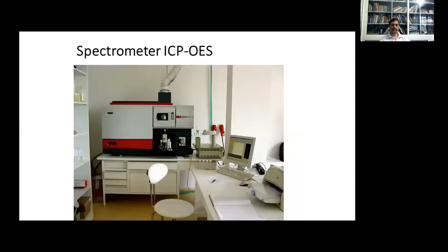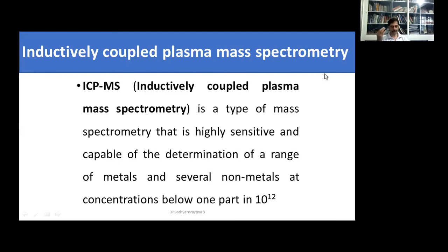And this is most useful for the analysis of Ayurvedic products, especially Rasaushadhis, because they are having highest sensitivity. This ICP-MS is a type of mass spectrometry that is highly sensitive and capable of determination of a range of metals and several non-metals at concentrations below 1 part per billion. At a concentration below 1 part in 10 to the power 12, when compared to atomic absorption spectrometry, which is commonly followed, which can determine you the particles up to parts per million. Here up to parts per billion, even beyond that, you can identify and also you can quantify.